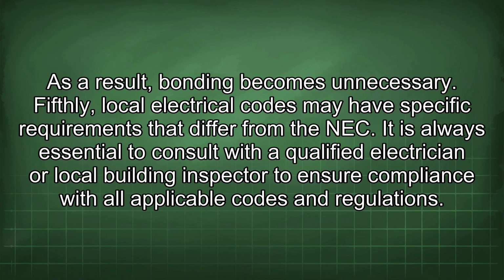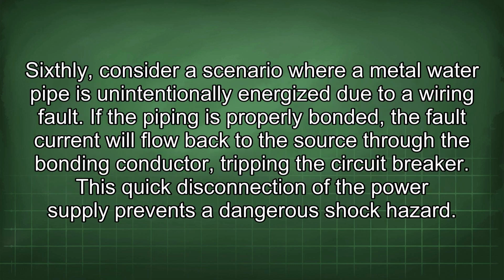Fifthly, local electrical codes may have specific requirements that differ from the NEC. It is always essential to consult with a qualified electrician or local building inspector to ensure compliance with all applicable codes and regulations. Sixthly, consider a scenario where a metal water pipe is unintentionally energized due to a wiring fault. If the piping is properly bonded, the fault current will flow back to the source through the bonding conductor, tripping the circuit breaker. This quick disconnection of the power supply prevents a dangerous shock hazard.